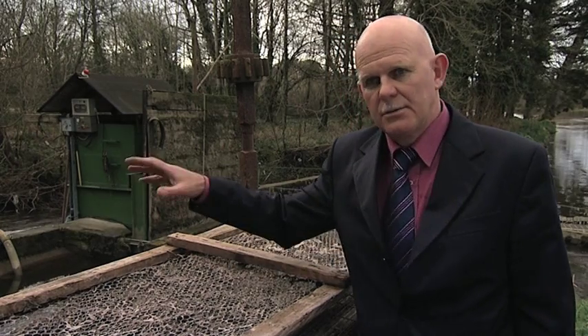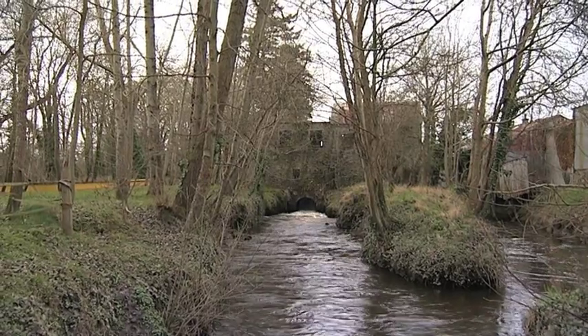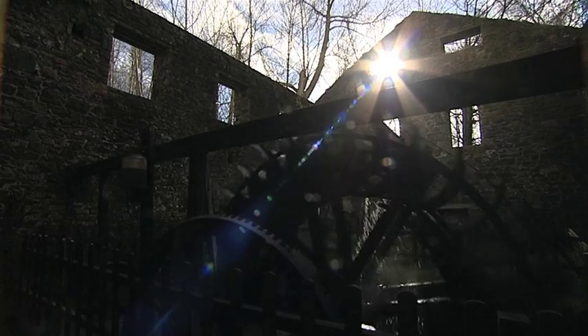The three different technologies here can all be built using local simple tools. They demonstrate completely different technologies that can be applied in various different circumstances. These can generate up to a maximum of about 2,000 kilowatt hours per day. In the old sawmill with the straight paddle wheels and mechanical drive, that would have produced about 100 kilowatt hours per day. We use some of that electricity in the mill and the surplus electricity is sold onto the ESB. That has been very successful and has been working for the past 16, 17 years.